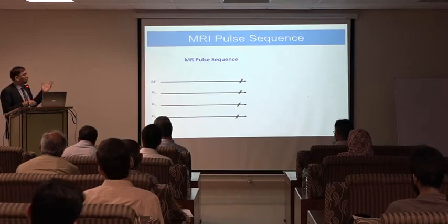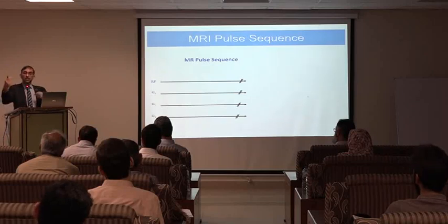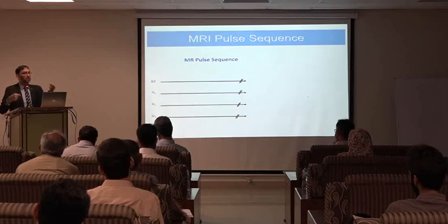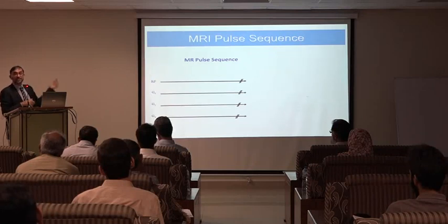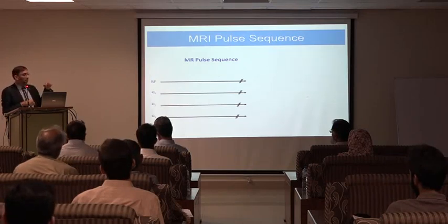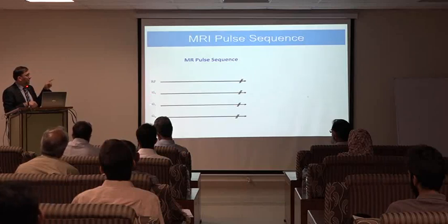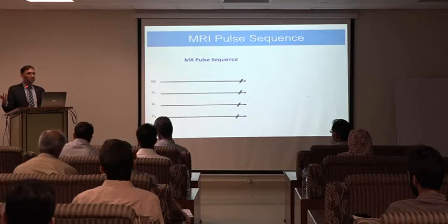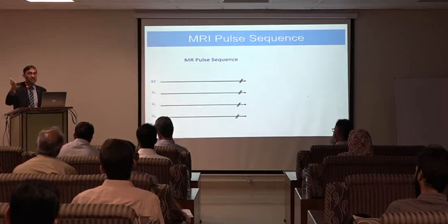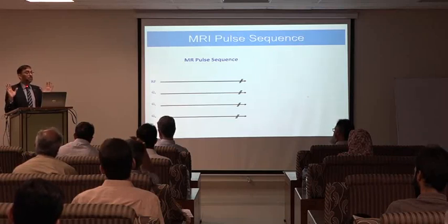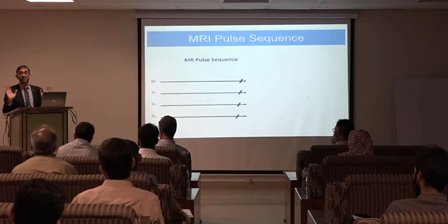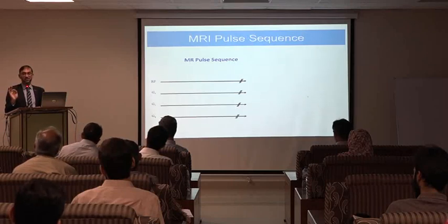So this axis shows the MRI pulse sequence. It's a process which shows which magnetic field will be applied at what time. Here you can see there is one RF pulse, the excitation pulse I was talking about, and then you have 3 gradients, GZ, GX and GY. These gradient fields are produced by other coils which produce variation of the magnetic field in the x-axis, the y-axis and the z-axis. Although that variation is only in milliteslas, much smaller, it has to be precise.